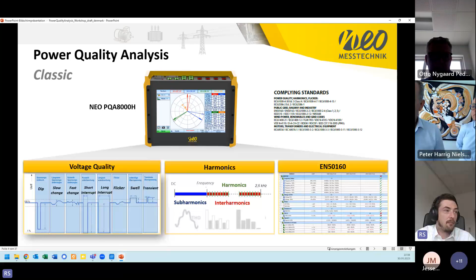But THD is actually a good topic to start with. Let's think about the classic analysis with a short example at an electric vehicle charging station where we want to measure some harmonics. If we think about THD, the total harmonic distortion, and compare this to the active power, we see that THD is rising when lowering the active power. So at 0.5 kilowatts we already have a THD of approximately 50%. This is because of the definition of THD, which relates to the fundamental frequency component.